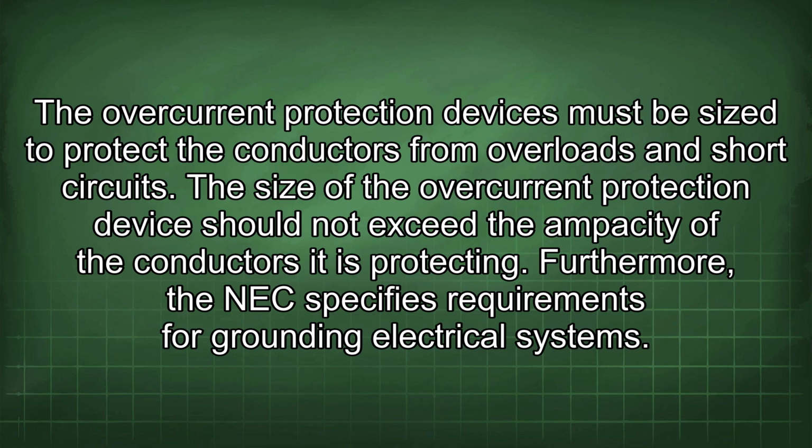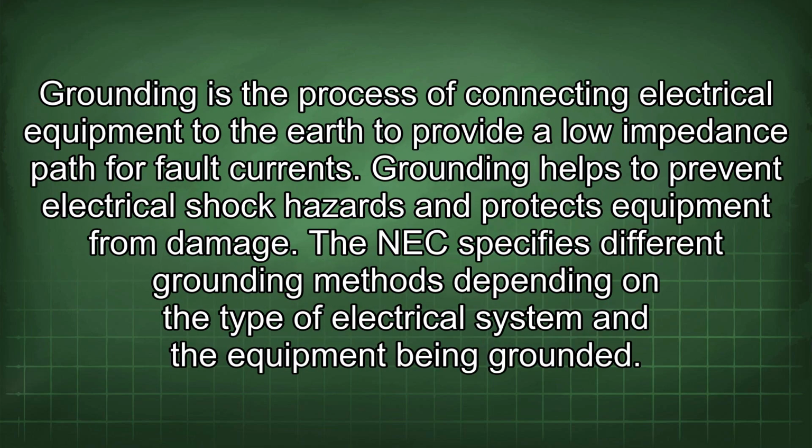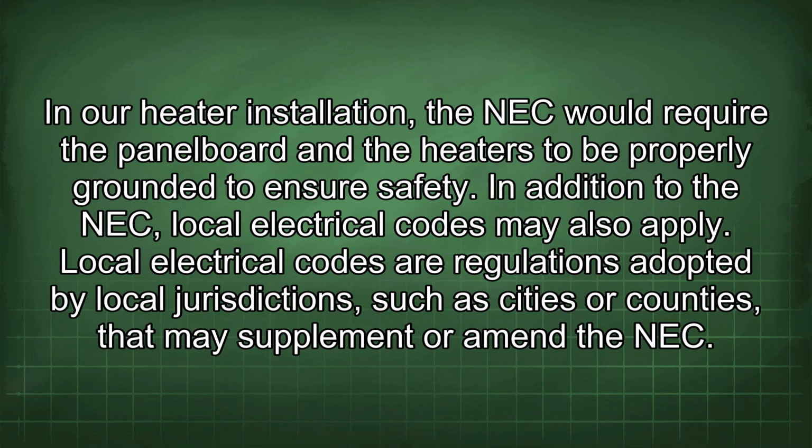Furthermore, the NEC specifies requirements for grounding electrical systems. Grounding is the process of connecting electrical equipment to the earth to provide a low impedance path for fault currents. Grounding helps to prevent electrical shock hazards and protects equipment from damage. The NEC specifies different grounding methods depending on the type of electrical system and the equipment being grounded. In our heater installation, the NEC would require the panel board and the heaters to be properly grounded to ensure safety.